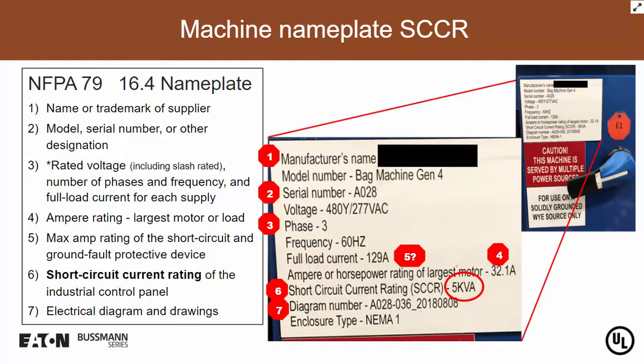And what we see here is a nameplate from a machine that has been identified by number to correspond with the numbers in paragraph 16.4 of NFPA 79. So you can see that a short circuit current rating, which is required as item number 6 in 16.4, is provided on this sample nameplate. We see number 6 identified on the nameplate, and it's 5 kV. I'm not sure why the A is there. That may be a little confusing, but actually, I'm sorry, the V is there, and I'm not sure why that's there. That could certainly be misleading. The rating is 5,000 amps, and so to have it marked as 5 kVA, that is not correct. But the intent here is to show that the nameplate does include the short circuit current rating.